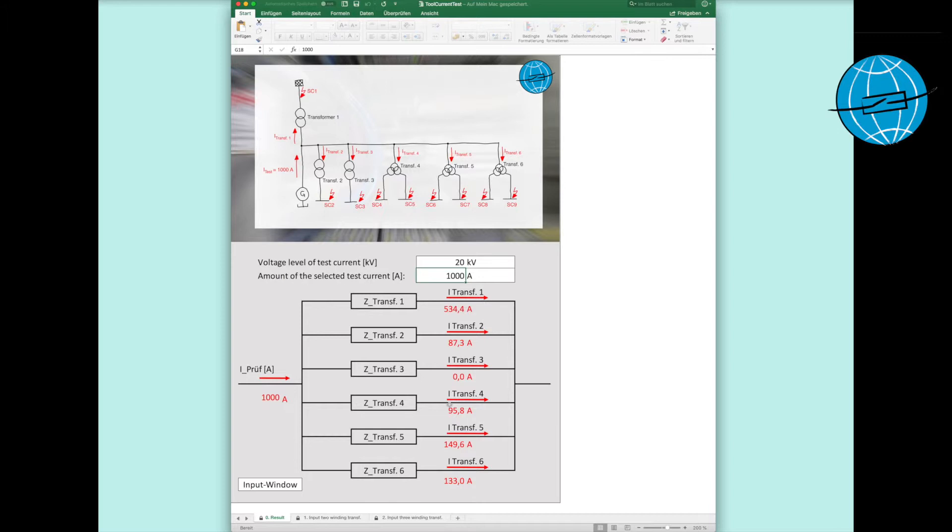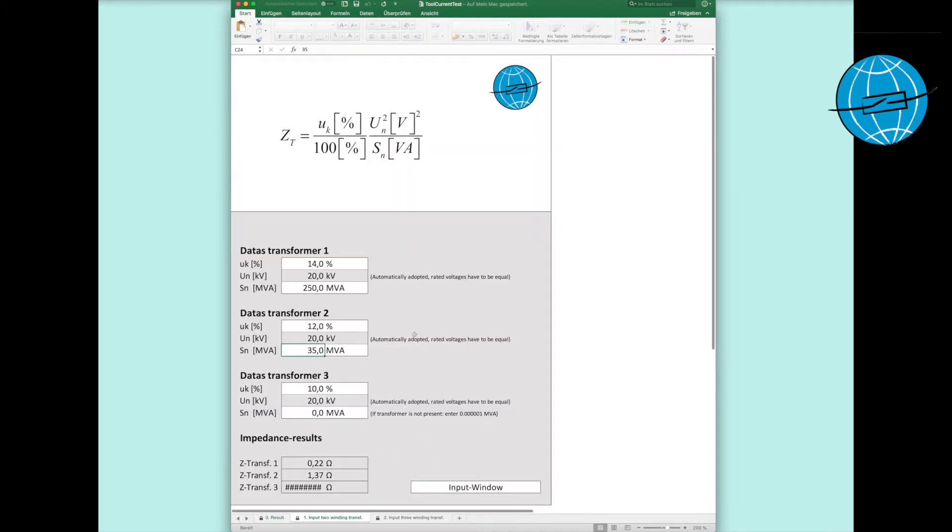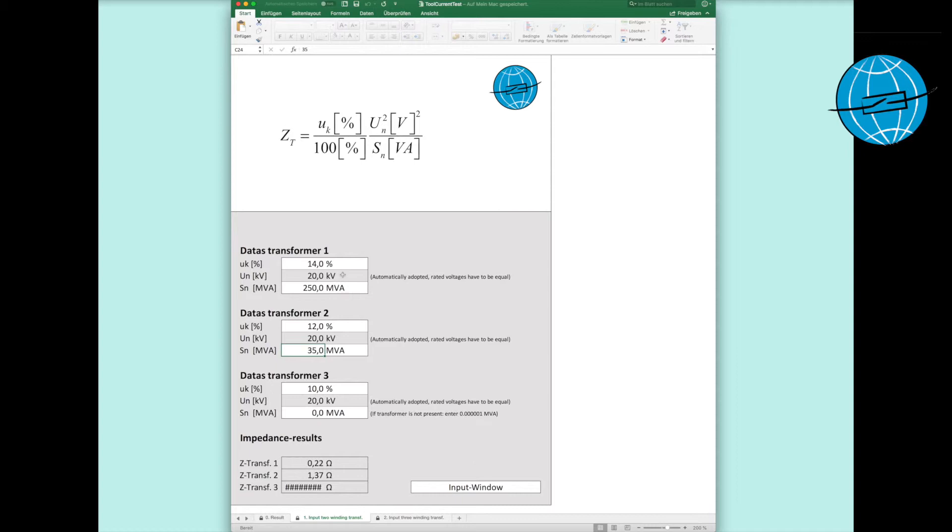The calculations are always based on the stored transformer data, which are entered on sheet 2 and 3. Let's take a closer look at sheet 2. Here, the short circuit voltages and the rated power of the two-coil transformers are stored. The nominal voltages are transferred automatically from sheet 1. If you want to exclude a transformer from the calculation, simply enter a nominal apparent power close to 0. In our example, we ignored transformer 3.